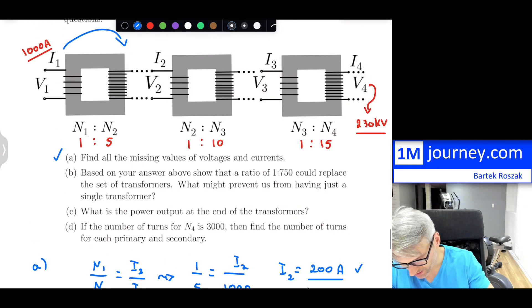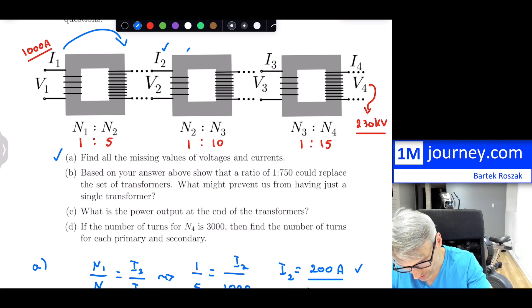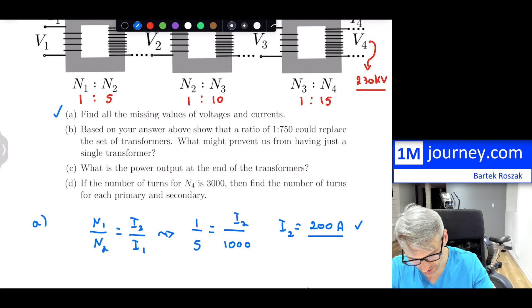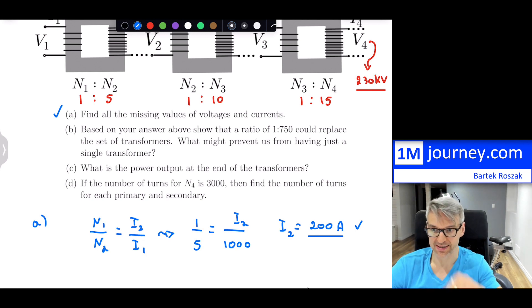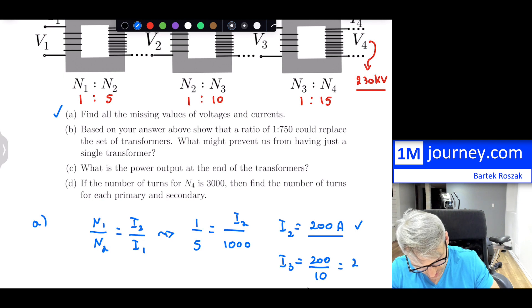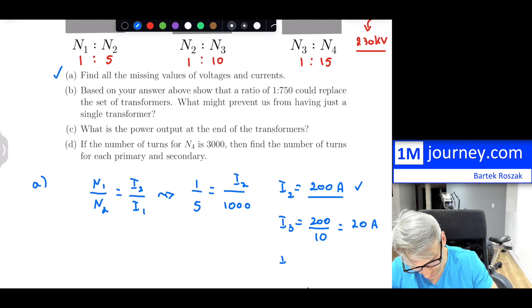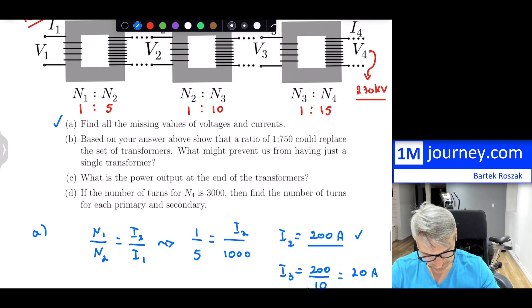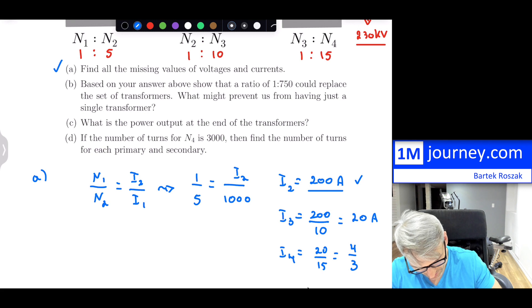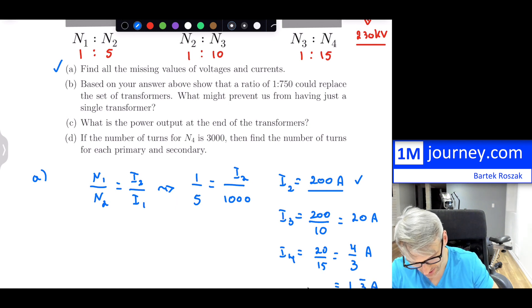Continuing with the currents: for N2:N3 = 1:10, starting with I₂ = 200 amps: I₃ = 200/10 = 20 amps. For N3:N4 = 1:15: I₄ = 20/15 = 4/3 ≈ 1.333 amps. Those are all the currents. Now for voltages, working backwards from V₄ = 230 kilovolts: N3/N4 = V3/V4, so V₃ = 230/15 ≈ 15.333 kilovolts.